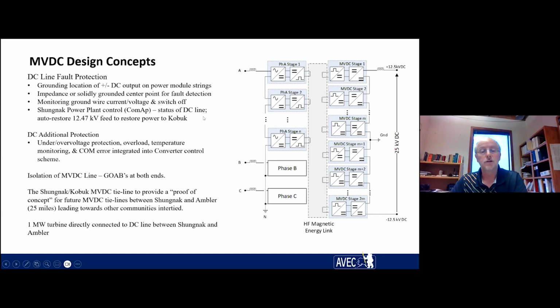So if there was an issue on the DC line, the Shungnak power plant ComAp control would auto restore, and then the 12 kV feed that's a backup would be restored to provide power back to Kobuk. The switches on either end of the DC line would then be isolated until we could locate the fault and restore power back on the DC. At this point, it'd probably be a manual operation to restore it back to the DC. Then there's additional DC protection on the converters under an overvoltage, overload, temperature monitoring, COM errors, and they'd be integrated into the control scheme.